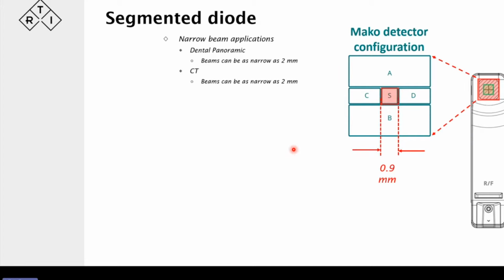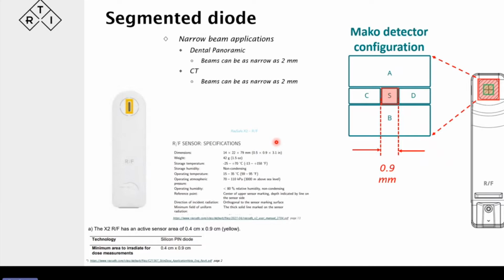And especially if we look at what we have on the market today, which is a detector which is 4 millimeters wide. And if you have a narrow beam, 2.5 millimeters, even 3 or 3.5, that detector will not be fully irradiated. So there is a substantial risk of underestimating dose to the patient. So that's a problem we solve with this segmentation of the detector. And it doesn't only underestimate the dose. Of course, you'll get an added uncertainty when it comes to HVL and KV measurements as well.